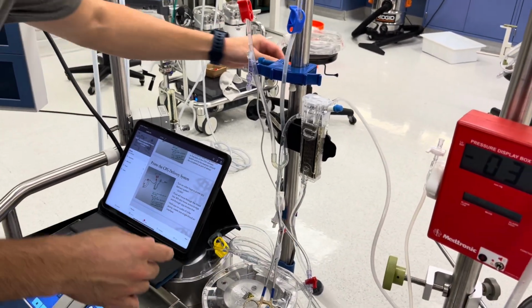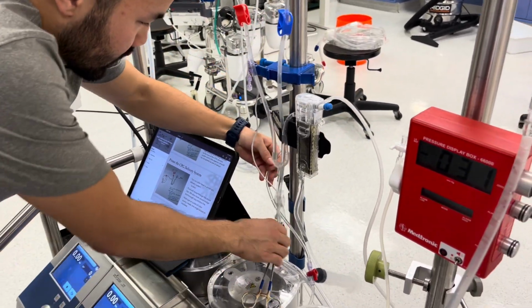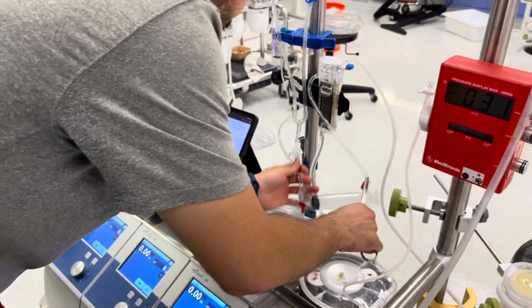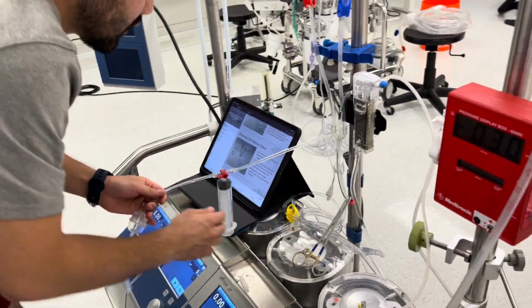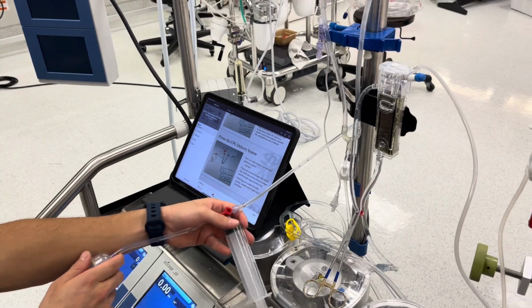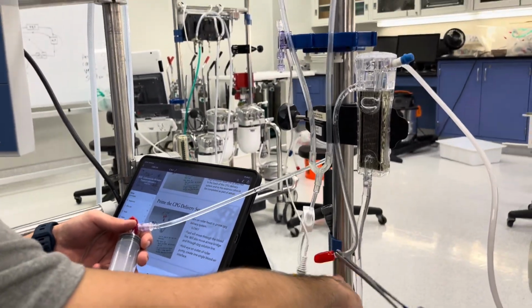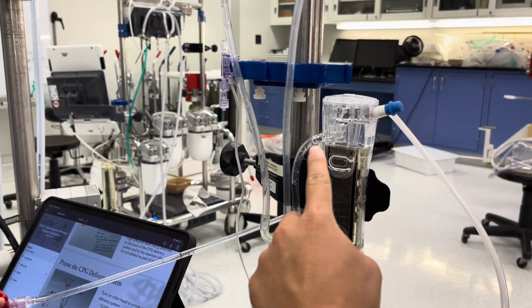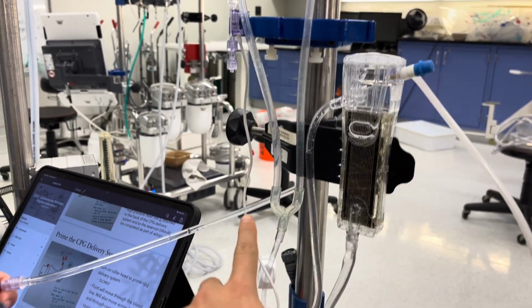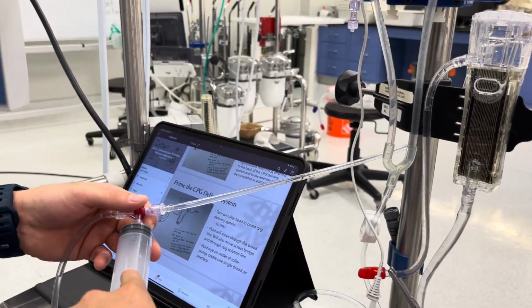The next thing that you're going to prime is your transducer line. So if the tubing had been working, once we had sent fluid through the patient delivery line, any excess fluid should have gone through here and filled up the syringe. Yep.